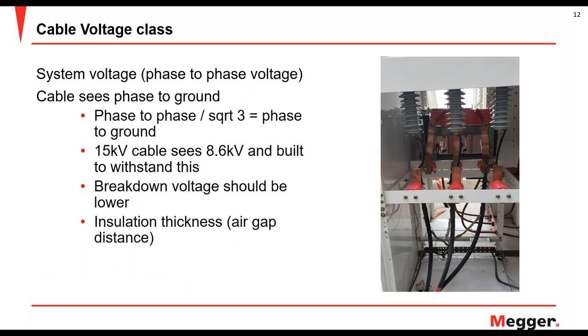On your different voltage classes, you need to know this when doing cable fault locating because you need to know how much voltage you can output onto your cable. A typical 15 kV cable gets about 8.6 kV operating voltage, and these cables are built to withstand that. Whenever your cable faulted, it was around operating temperature because it was in service when it failed. So nine times out of ten, you typically have a pinhole fault — there's a gap in the insulation that can arc over itself, and you have to overcome the thickness of the insulation where that little air gap is to get it to flash over to your concentric neutral.